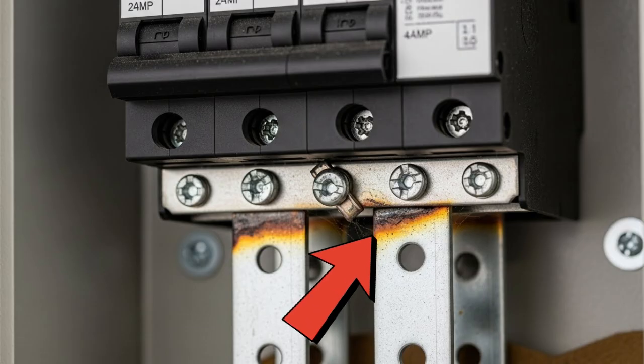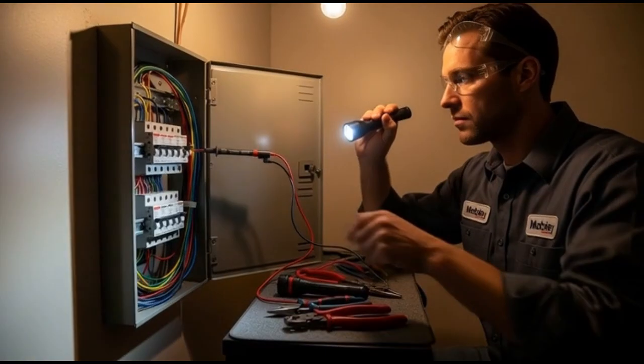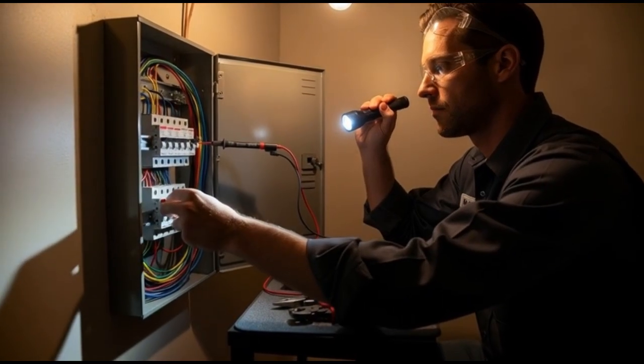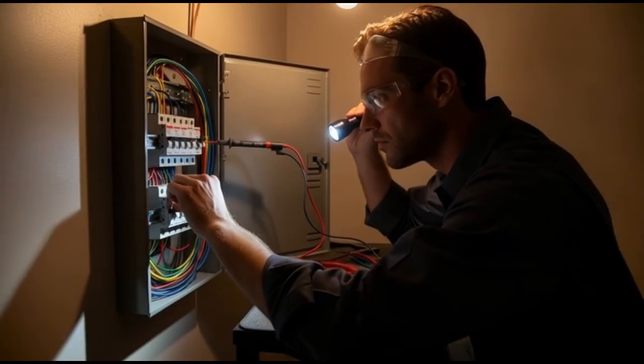Left unchecked, this can melt plastic components, damage the bus bars, or ignite surrounding materials. If your main breaker trips and the panel feels warm to the touch, or you notice a burning smell near the panel, a loose bus bar connection is a prime suspect. This requires immediate attention from a licensed electrician.